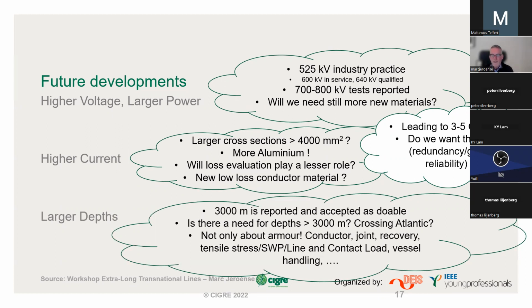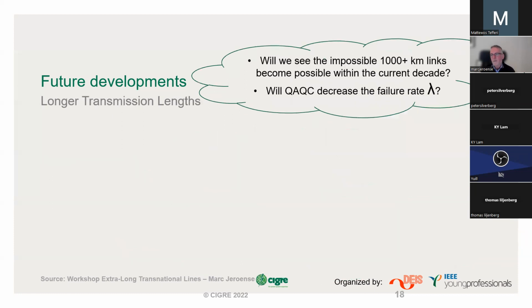Let's first do 3,000. But there's also an old dream of some people, which I could challenge, to lay cables across the Atlantic. If one does so, one would need depths far beyond that. Again, it's not only about the armor, it's the complete package that has to be thought about when developing cable systems for these depths: the joints, the recovery, the repair, the stresses in all the components, the sidewall pressures, contact loads. So it's lots of mechanics that goes in there.